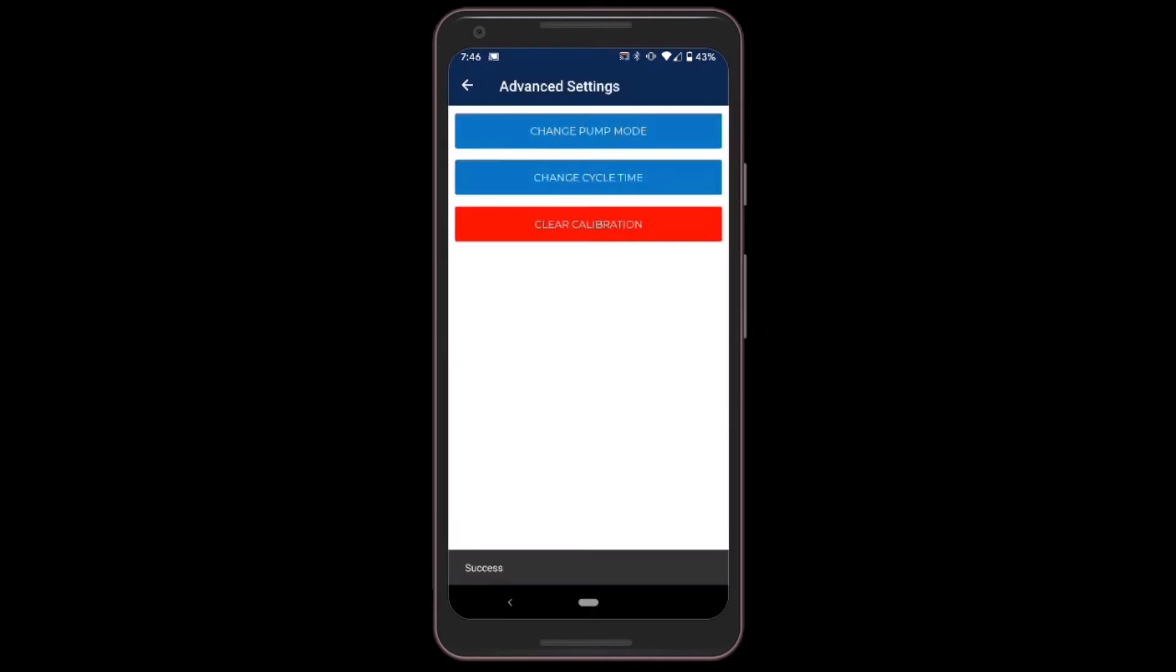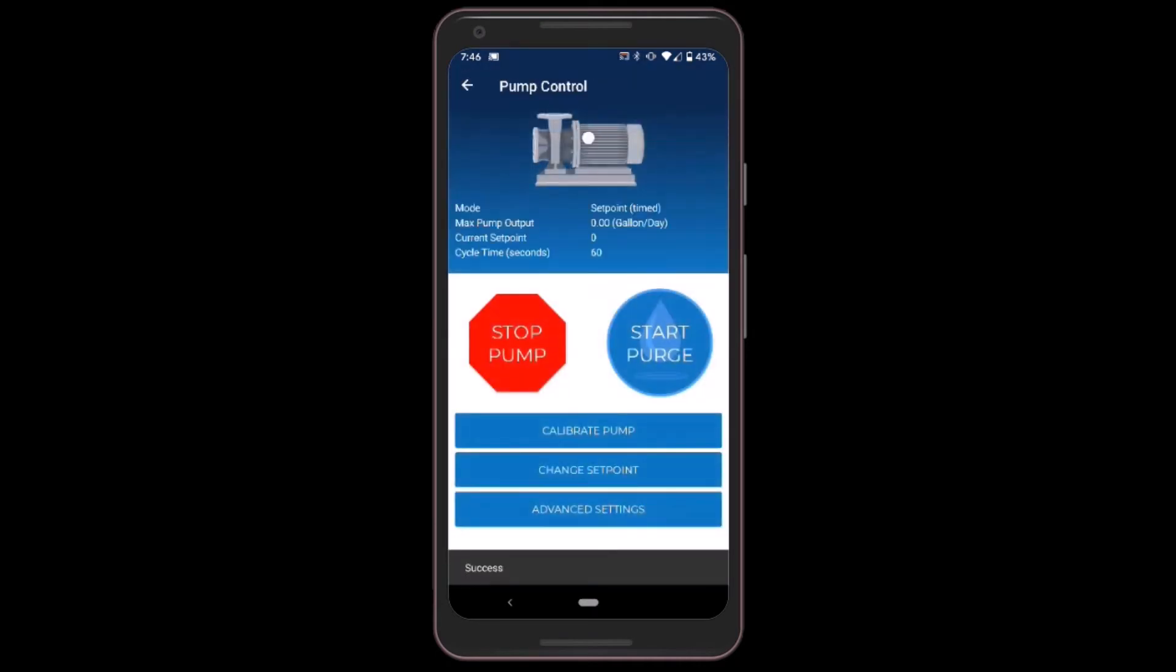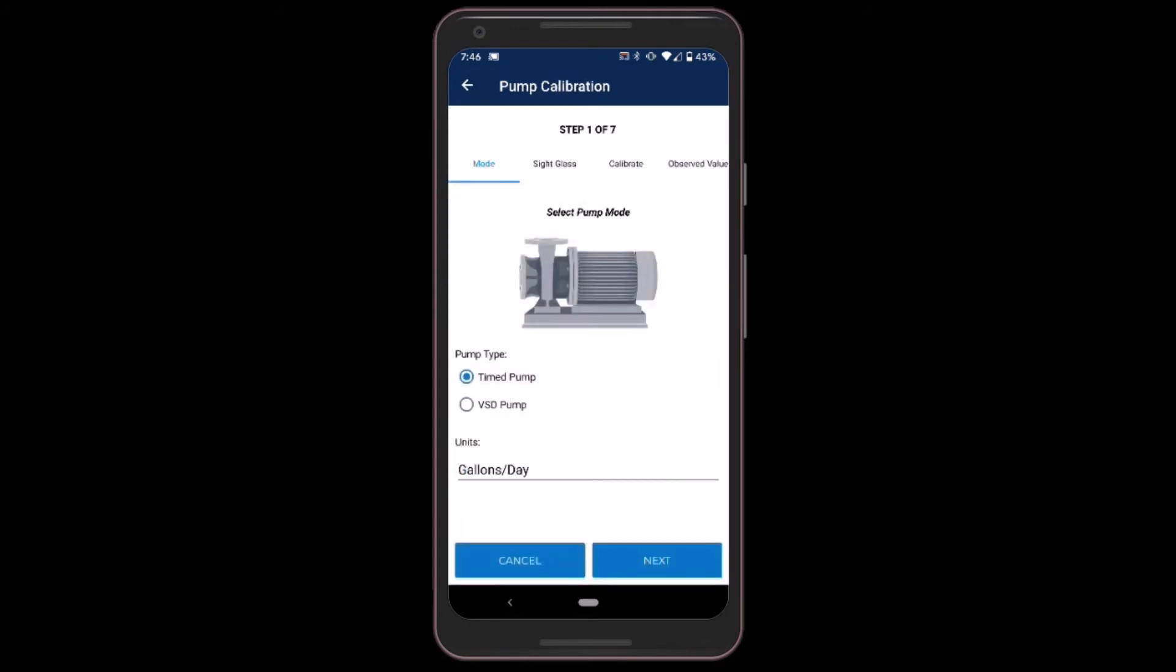So go back and I will click Calibrate Pump. Now this is a really simple process. The first thing I need to do is select the type of pump. In this case this is a timed pump, which means it uses a single speed motor with an on-off duty cycle to achieve an injection rate set point. I'll click next.